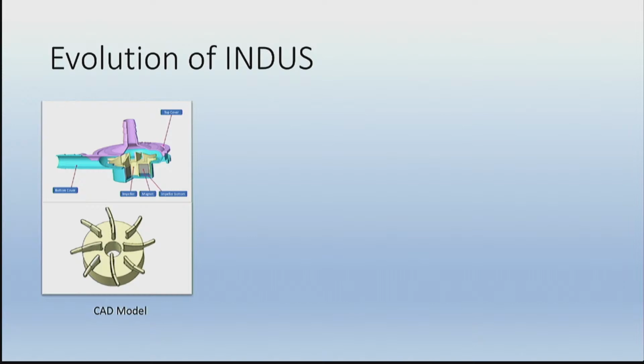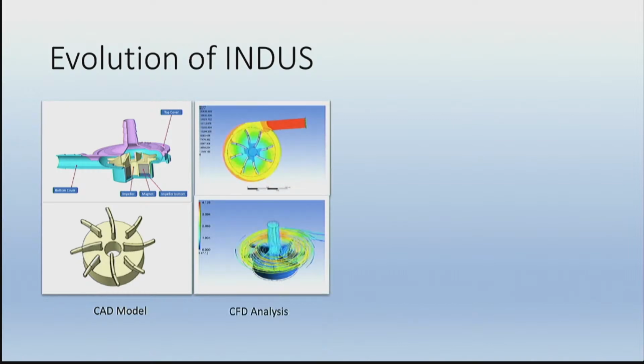First we design the components in the software. Then we do the CFD analysis. Designing is the easiest part. We can design anything and everything that we want in the software. But analysis has to be done for the fluid dynamics, which is where the engineering comes into the picture. We cannot directly manufacture any component with the design that we get. The fluid dynamics, the pressures, the flow rates, and the shear stresses need to be evaluated so that the blood does not get damaged. So the second step is the CFD analysis.